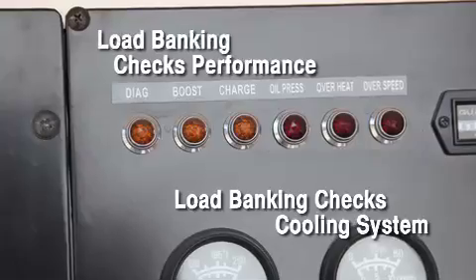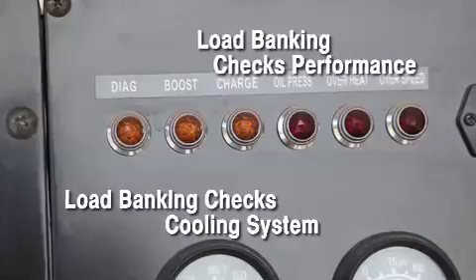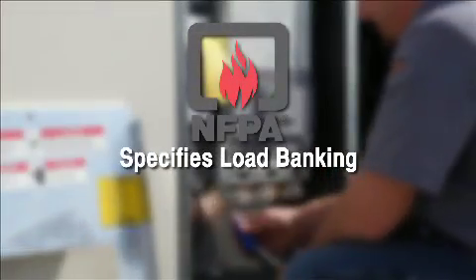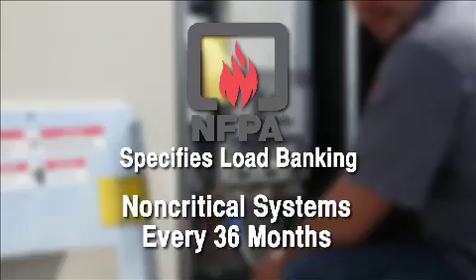Only a load bank test can load the system to full capacity, attain the temperatures needed to test the cooling system, and burn off harmful excess fuel and carbon deposits. The National Fire Protection Association recommends annual load bank testing of critical load generator set installations. For non-critical systems, NFPA 110 recommends load banking every 36 months.